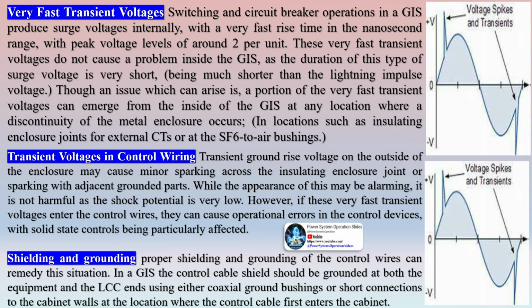Very fast transient voltages: switching and circuit breaker operations in a GIS produce surge voltages internally, with a very fast rise time in the nanosecond range, with peak voltage levels of around 2 per unit.